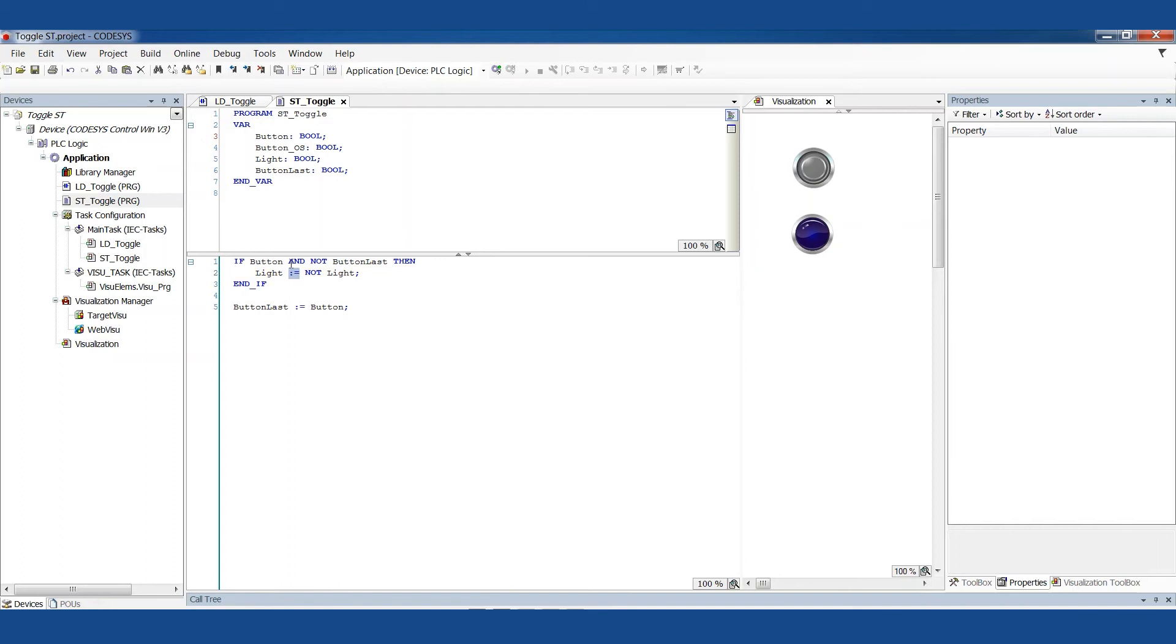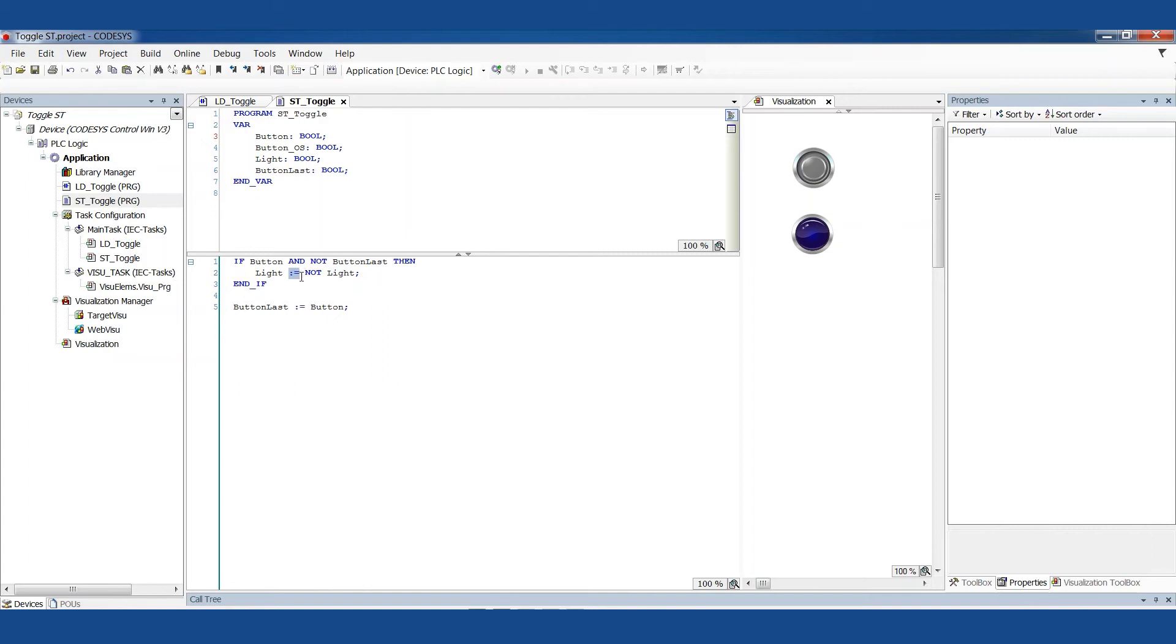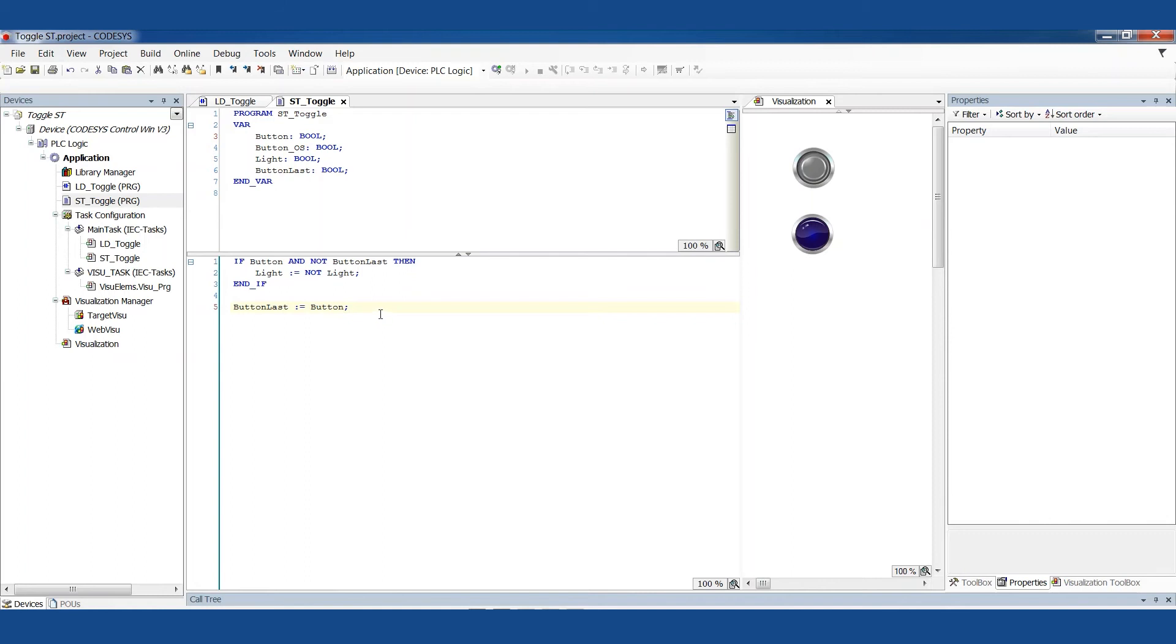I don't know if I mentioned this in any other videos, but this is another thing that I found a little bit strange just based on my time with other text-based languages. This is the assignment operator in structured text. This is the standard that's defined by IEC 61131. So any environment that implements structured text uses this same standard. And really, all of this will look very, very similar across environments. Colon equals just means take this thing on the right side and stick it into the thing on the left side.